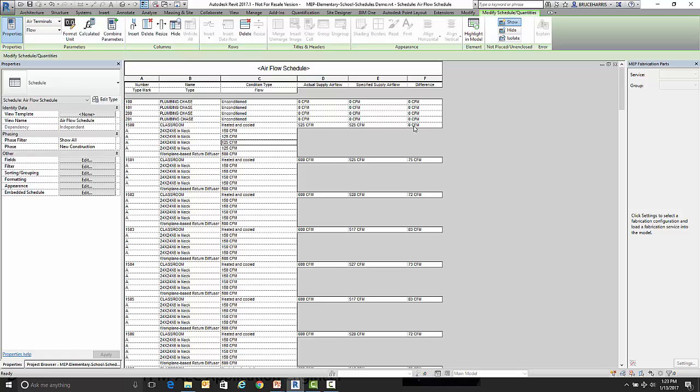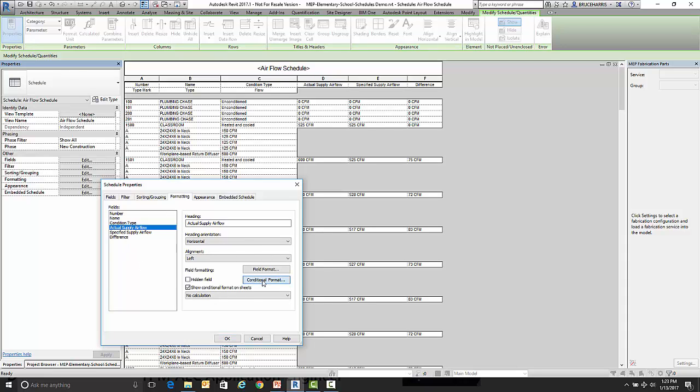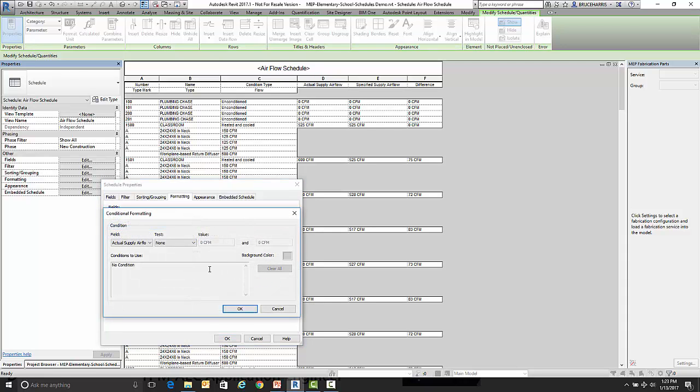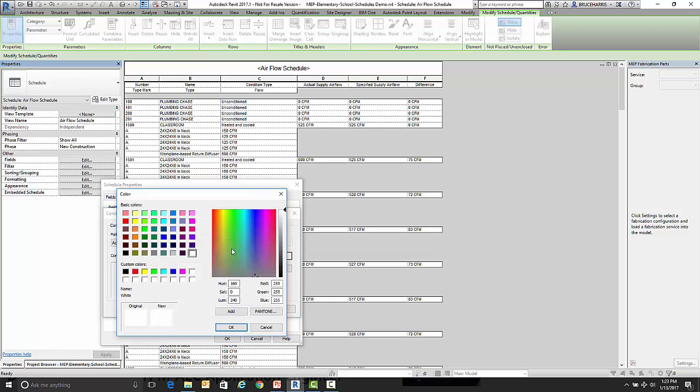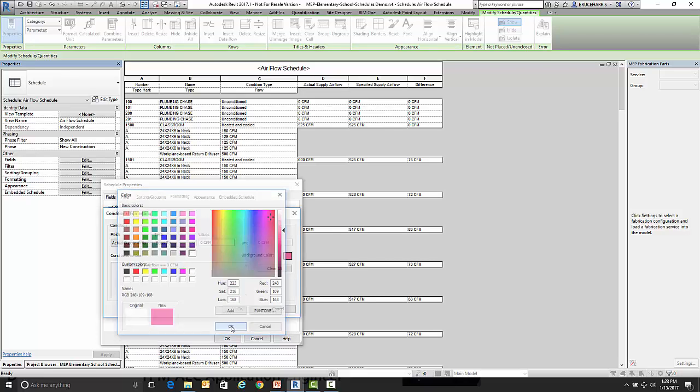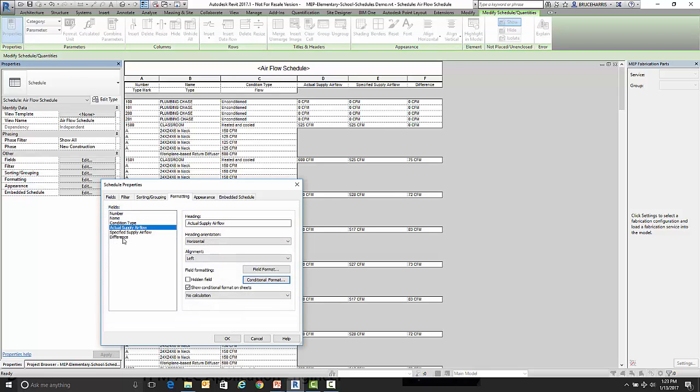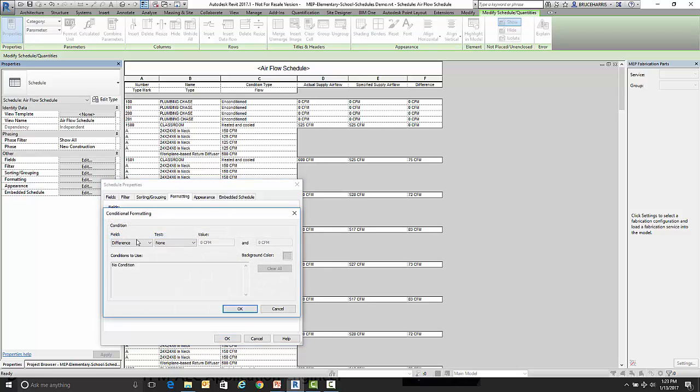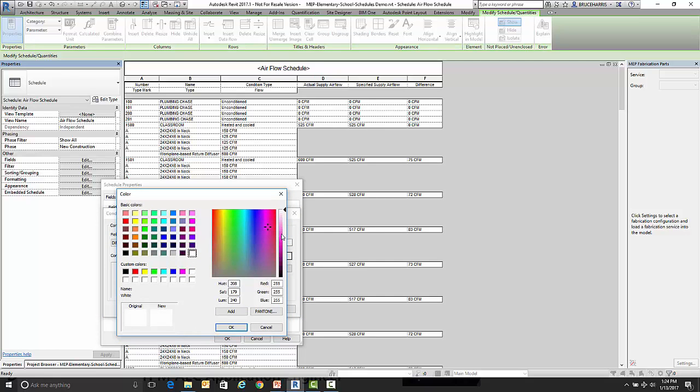Now it would be easier if I had something that would point out when I had an issue here. So what I'm going to do is come back in here and go into formatting. And I'm going to format a couple of different things. The first thing I'm going to format is actual supply airflow, and I'm going to do a conditional format for it. And I'm going to say if it's equal to zero, then I want to give it kind of a reddish color. Now I also want to do the same thing for difference, except I'm going to make my condition a little bit different. Instead of a specific value, I'm going to say it's not between negative 25 and 25 CFM. And we're going to make that background color a similar color.